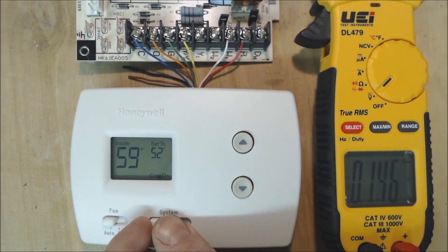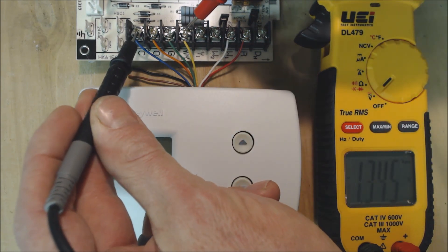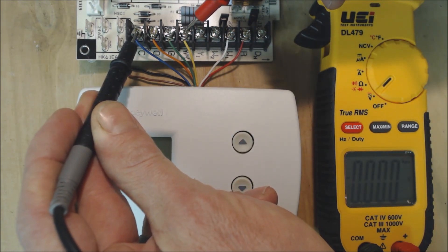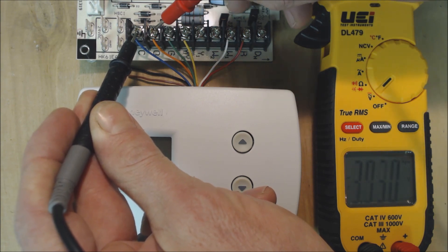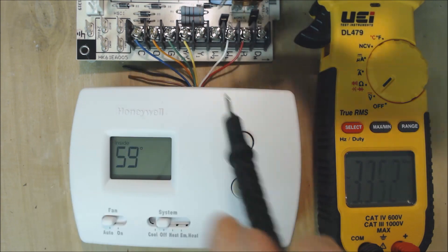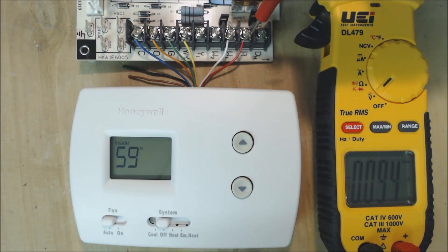Now let's turn this off. We no longer have 24 volt power between Y and common, G and common, or O and common. That was all happening because the thermostat was connecting all of those together with the R wire.